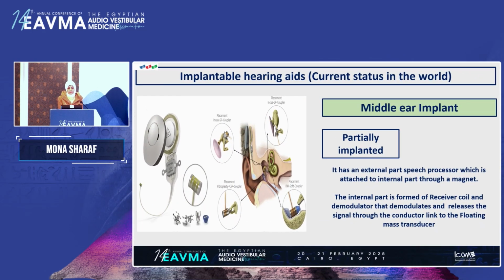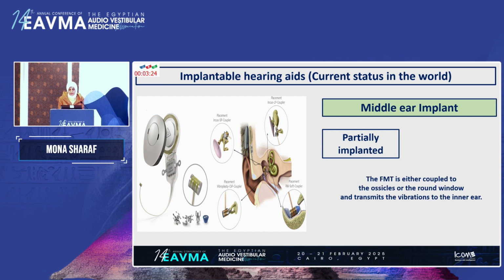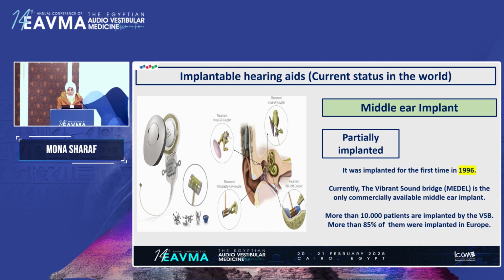The partially implanted middle ear implant has an external part, or external speech processor, which is attached to an internal part through a magnet. The internal part is formed of a receiver coil and demodulator, which demodulates and releases the signal through a conductor link to a floating mass transducer. The floating mass transducer is coupled to the ossicles or the round window and transmits vibration to the inner ear. They were implemented for the first time in 1996, and currently the Vibrant Soundbridge is the only commercially available middle ear implant. According to the Med-El headquarters, more than 10,000 patients are implanted with the Vibrant Soundbridge.